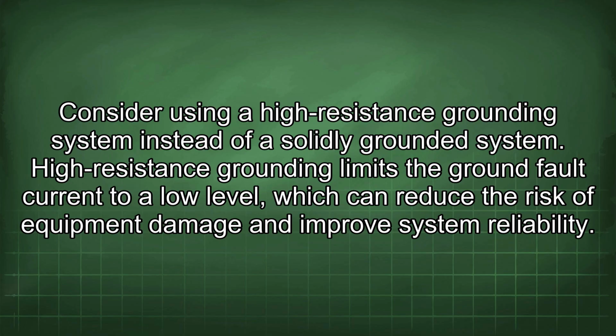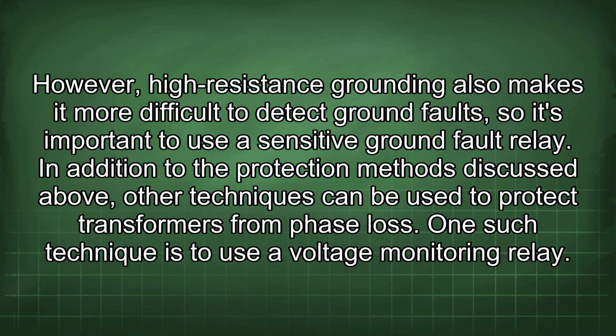High-resistance grounding limits the ground fault current to a low level, which can reduce the risk of equipment damage and improve system reliability. However, high-resistance grounding also makes it more difficult to detect ground faults, so it's important to use a sensitive ground fault relay.